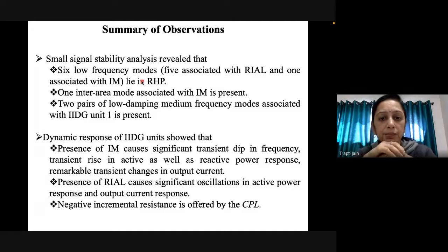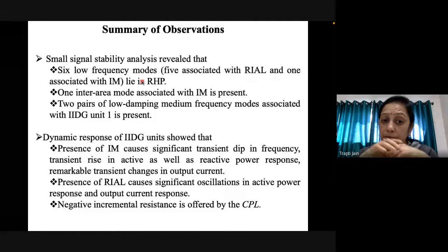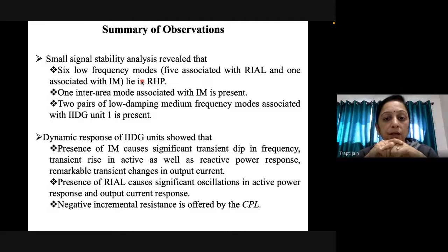Now the dynamic response of IIDG units showed that presence of induction motor causes a significant transient dip in frequency, transient rise in active as well as reactive power response, and remarkable transient changes in output current. Presence of RIAL causes significant oscillations in active power response and output current response, and negative incremental resistance is offered by the CPL.